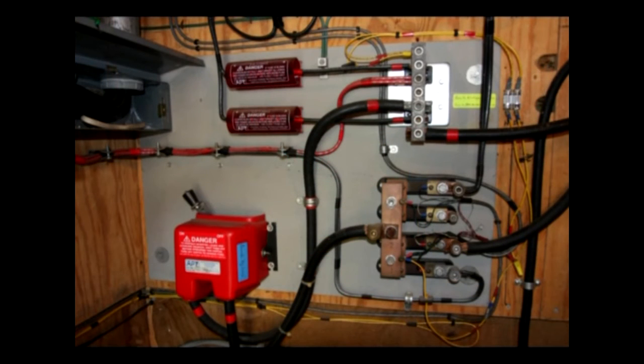Instead of a box, we have an actual building, so this equipment - our charge controller, inverter, and switches - are mounted right on the wall on insulating surfaces. You can see on the bottom left the big red switch with the fuse inside, coming from the batteries. It's got a very large wire coming in from the batteries because they're going to the inverter, and that comes up to 2 buses on the right.